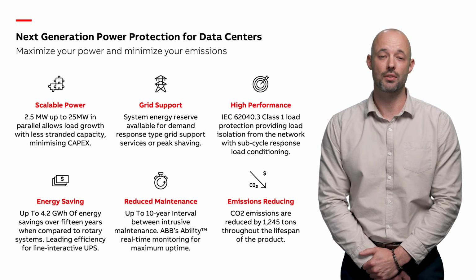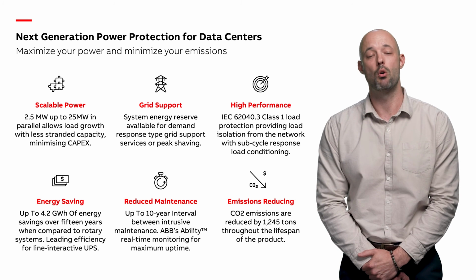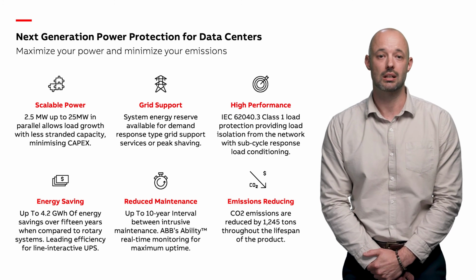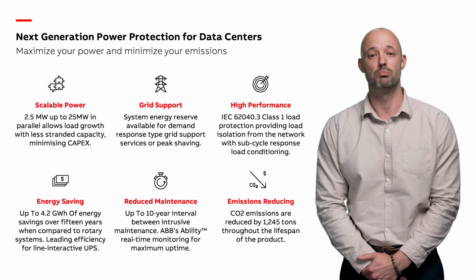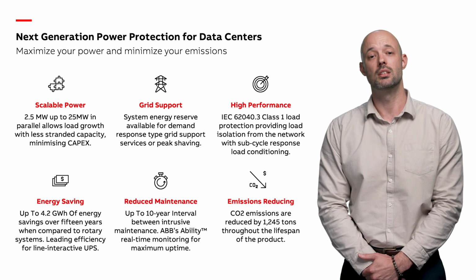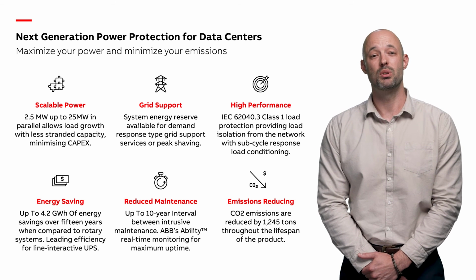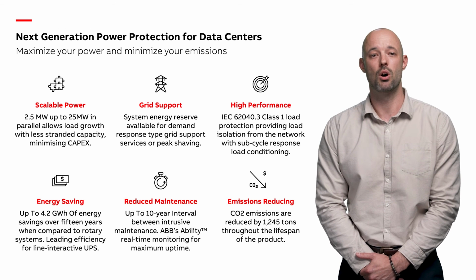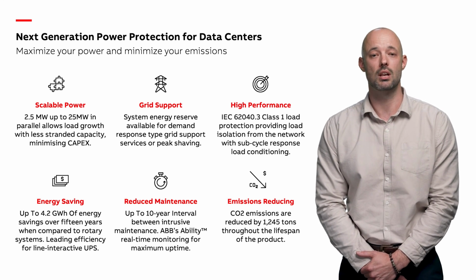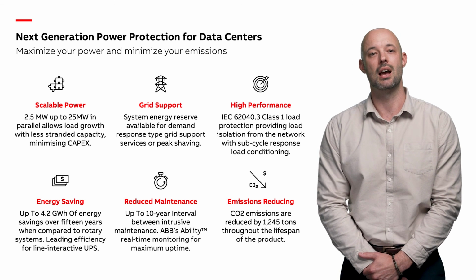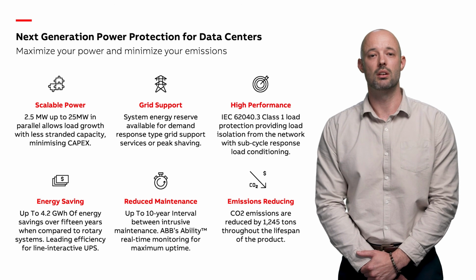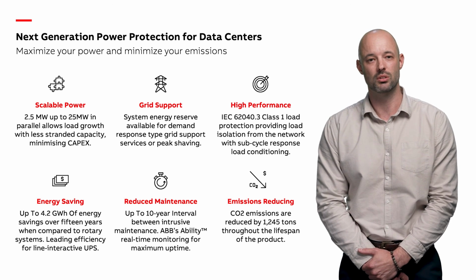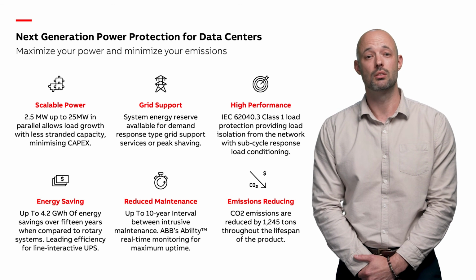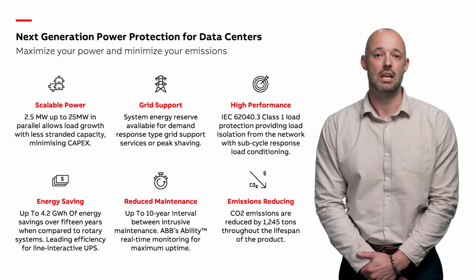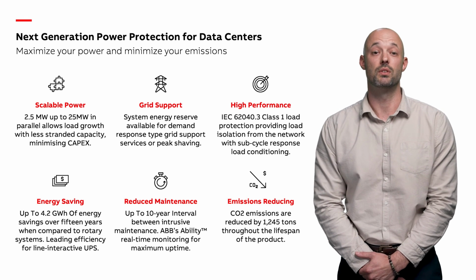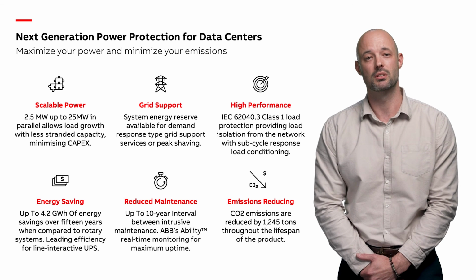As has been demonstrated throughout this webinar, significant advantages can be gained while operating protection at the medium voltage level. Class 1 protection can be maintained whilst minimising distribution losses and enabling a significant reduction in copper use. ABB's extensive capabilities in delivering multi-megawatt critical facility protection ensures your organisation can achieve its sustainability ambitions at scale. The HiPerGuard MV-UPS provides the opportunity to participate in grid support services, including demand response, contributing to overall grid stability and reliability. This provides a means for additional revenue streams for the facility owner to meet business sustainability objectives.